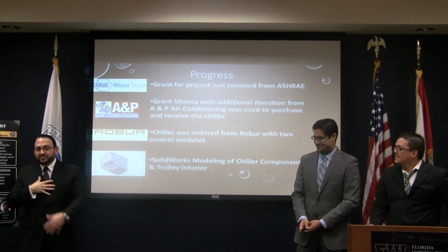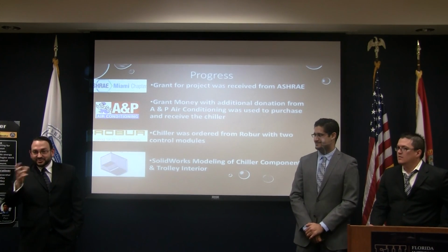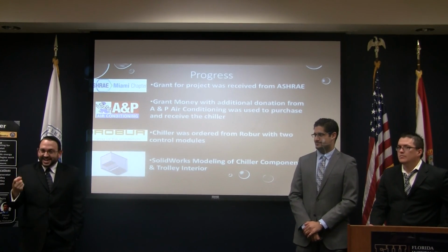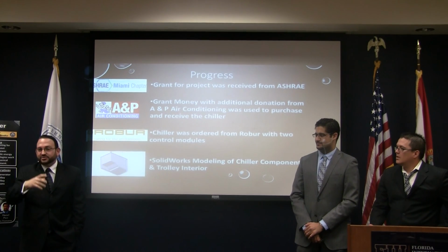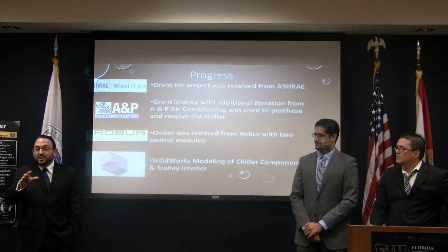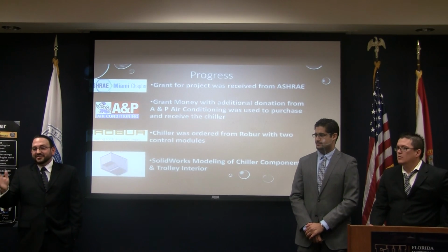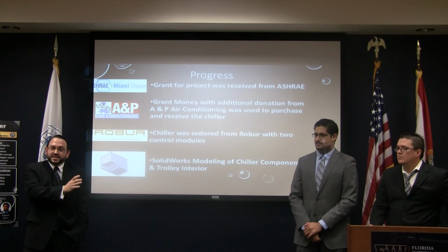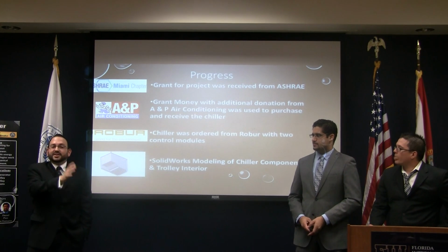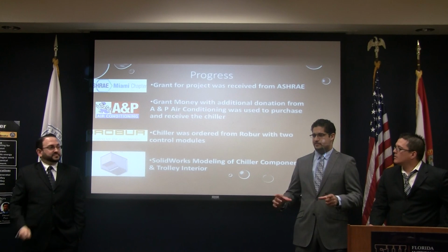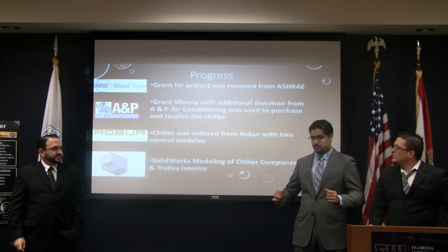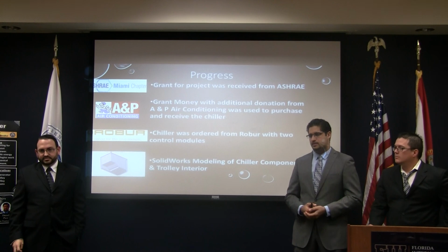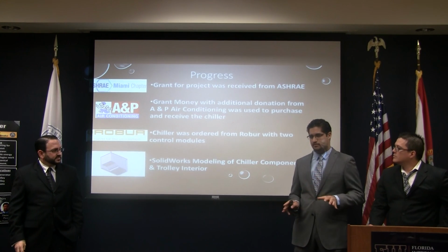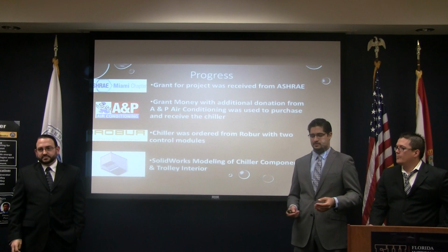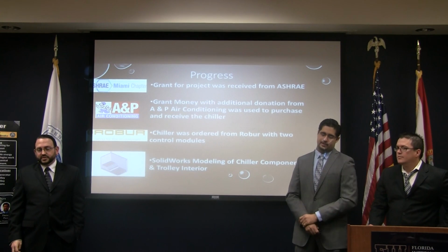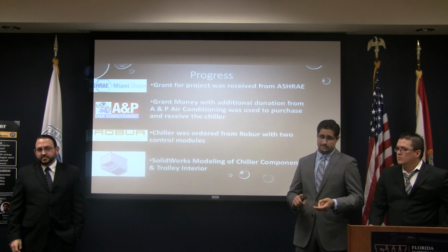For reference, I'm an air conditioning contractor, so we typically deal with internal vibration using rubber mounts and spring mounts for our systems — so half of the equation is already answered, since our system doesn't vibrate by itself. What remains is keeping our system steady with the movement of the trolley. That's why we feel separating it into its own frame and shock-mounting that to the chassis of the trolley is the best approach, since within those components there's little or no vibration. Mounting them separately keeps everything nice and isolated, both vibration and thermal.